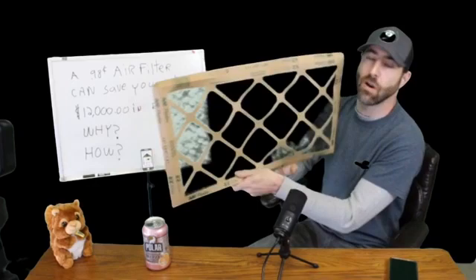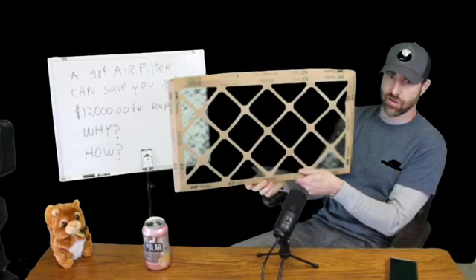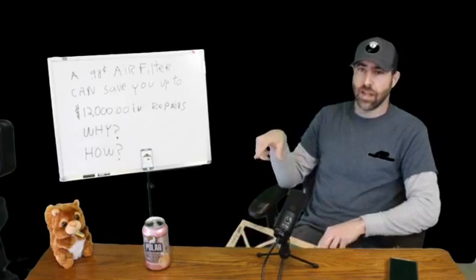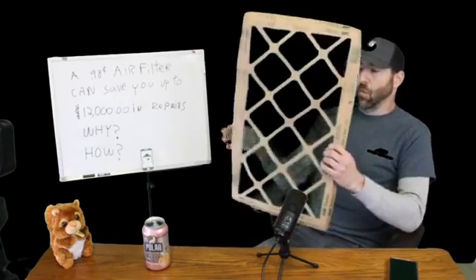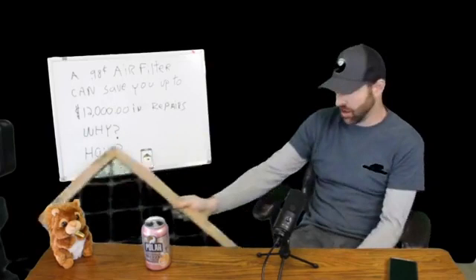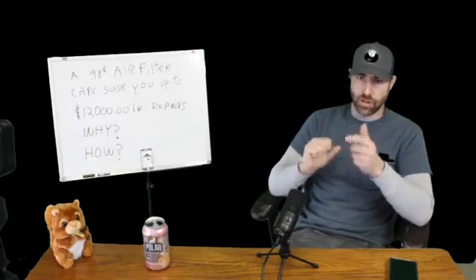Right before the evaporator coil, you have this after the return ducts. So you have this that protects your coil, which is a thin tube coil. And that's where all the refrigeration flows through, from the evaporator, through the line sets, out to your compressor and condenser. So basically, when this thing gets really dirty and turns like this, it clogs your entire system. You're gonna block the airflow, and then it's gonna cause a heavy load on your compressor, and it can burn out your compressor, which can burn out your electrical system, can burn out your fans, and your whole system is done. All because of a 98-cent filter.